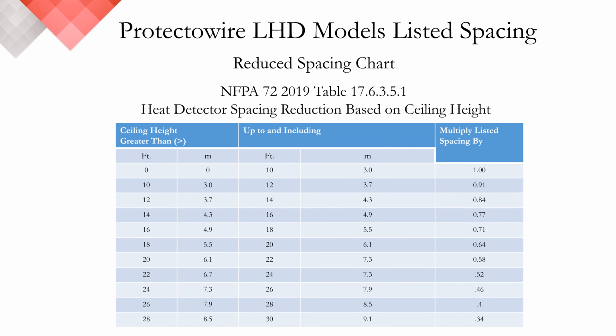As we discussed in the previous slide, all series of Protectowire linear heat carry some form of recognition from FM and UL, whether it's open area spacing or simply special hazard proximity detection. To further our discussion on listed spacing, it's important to understand how the spacing guidelines are applied when it comes to heat detection. The spacing rules for heat detection are defined in NFPA 72, Chapter 17. More specifically, Chapter 17.6.3 under the heading Location and Spacing.